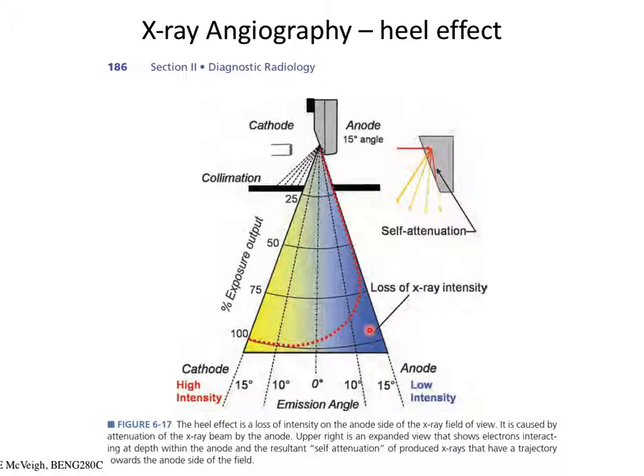There are systems being designed with multiple x-ray sources around the patient simultaneously getting views at different locations. There's probably a smarter anode geometry that could nullify the heel effect, but as far as is known, everybody just deals with it.